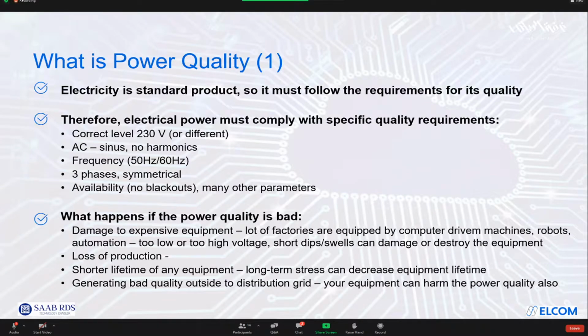So a lot of equipment can be damaged by wrong power quality. On the other hand, your factories or your consumption, if not well engineered, can also harm the power quality of the grid itself. So, for example, if there are some welding machines or something with really huge power input, it can generate a non-sinusoidal current, and these higher harmonics on the current, if high enough, can also generate higher harmonics on the voltage on the grid.